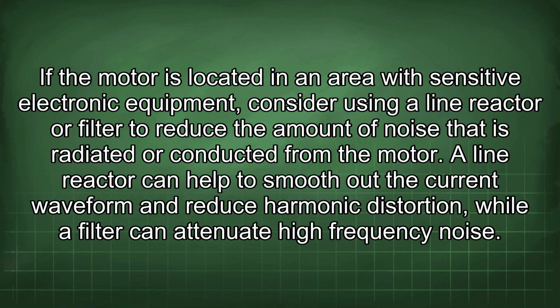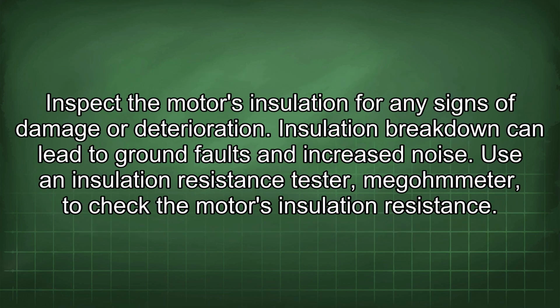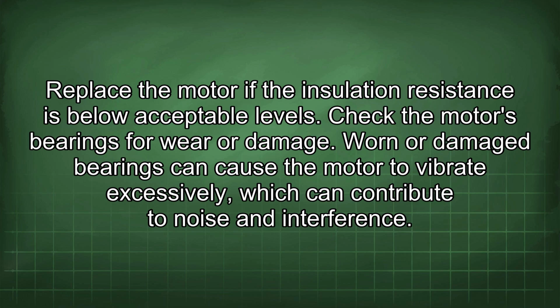A line reactor can help to smooth out the current waveform and reduce harmonic distortion, while a filter can attenuate high-frequency noise. Inspect the motor's insulation for any signs of damage or deterioration. Insulation breakdown can lead to ground faults and increased noise. Use an insulation resistance tester, megohmmeter, to check the motor's insulation resistance. Replace the motor if the insulation resistance is below acceptable levels.